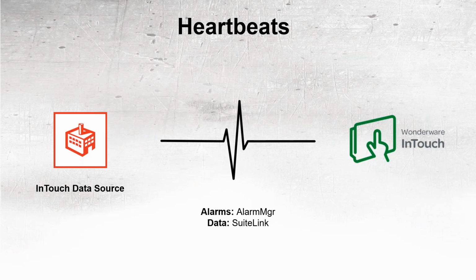We're using Wonderware's Alarm Toolkit to do that. And to get data from InTouch, we're using SuiteLink. So technically, this is two different connections. The heartbeat goes through the SuiteLink connection. All the alarms come from the Alarm Manager connection. So it's both of these connections together that make the direct connect possible.